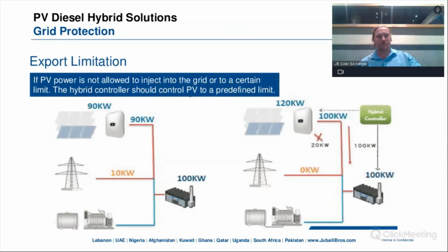And then also export limitation to the grid, because you can have this solar, diesel, and grid, a hybrid of all three power sources. So the fuel save controller will prevent export to the grid. So this is a very great function because you can have solar as your primary source of energy, you can have grid as your secondary source of energy, and you can have diesel as your backup supply only. And the fuel save controller will prioritize in this way, and it will also prevent power from going back into the grid.